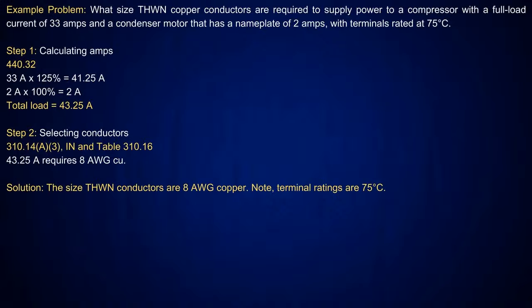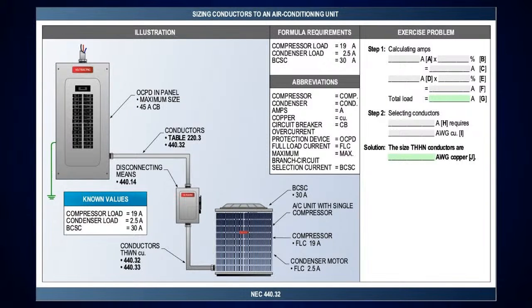Now, as I look at this AC unit, same thing. I've got a 19 amp compressor and a 2.5 amp condenser. How do I do it? 19 amps is at 125%. The condenser is at 100%. Add all those amperages up. Then size your conductors based on table 310.16 and the 75 degree C column.